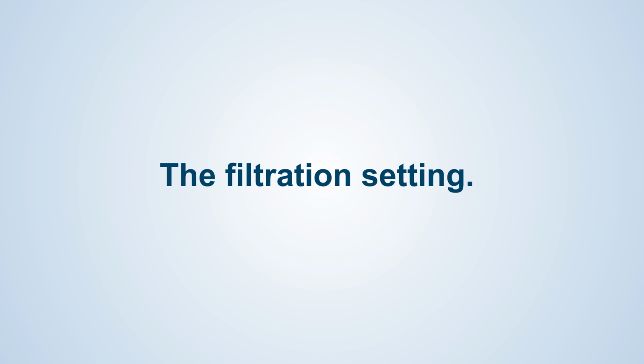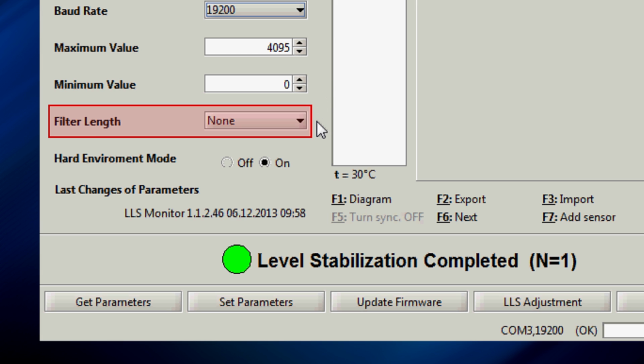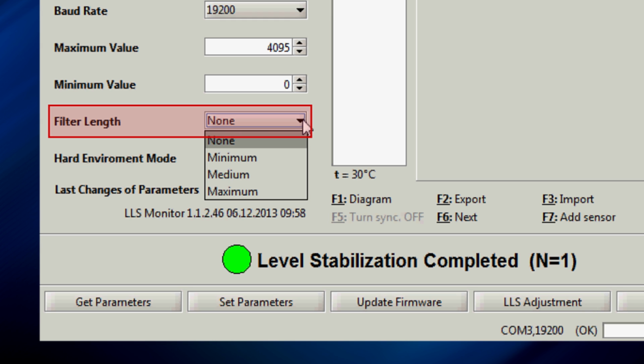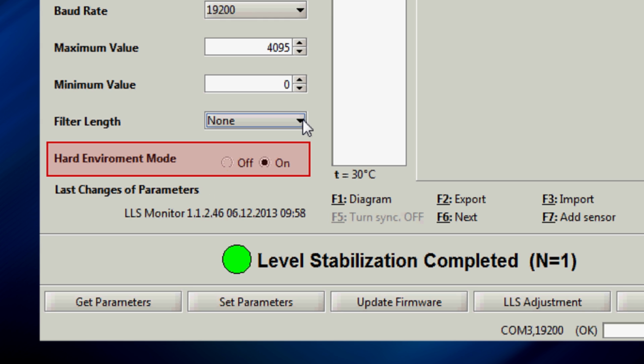The filtration setting. Filtration is a process of automatic elimination or smoothing of fuel level fluctuations. We recommend disabling this setting for stationary tanks only. One of the filtration setting values must be selected for vehicles. In case of heavy-duty vehicles operated on farmland, in mines or quarries, we recommend enabling the hard environment mode additionally.